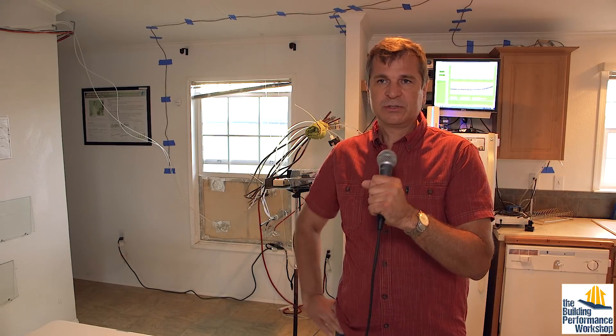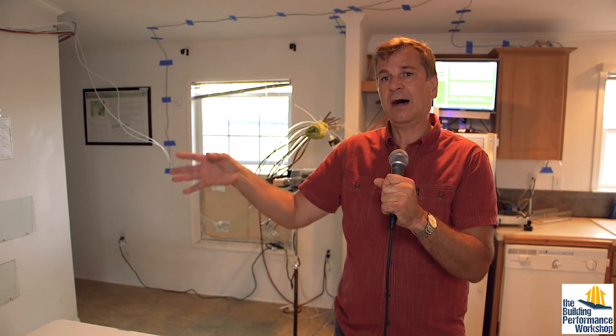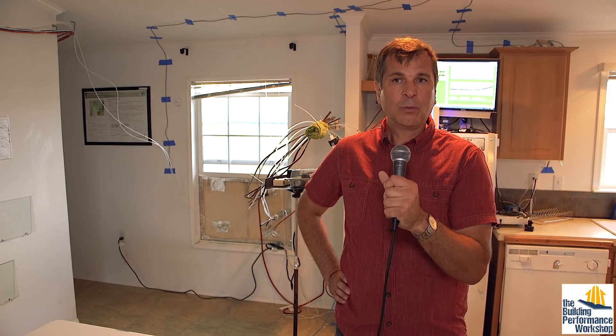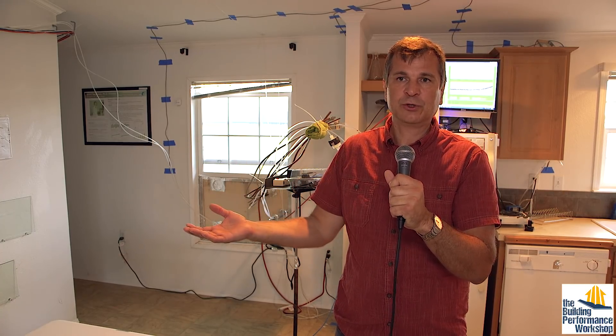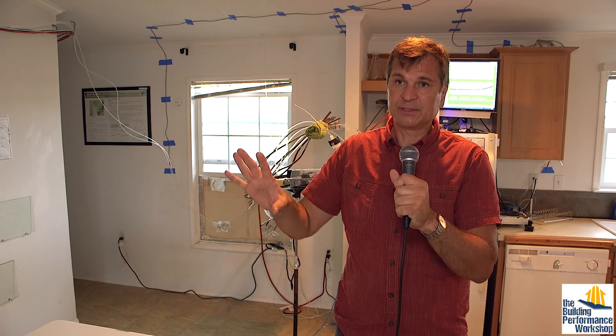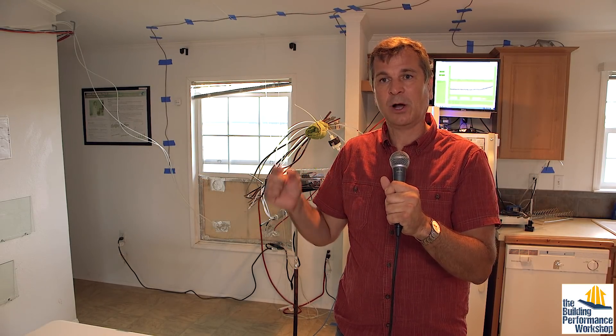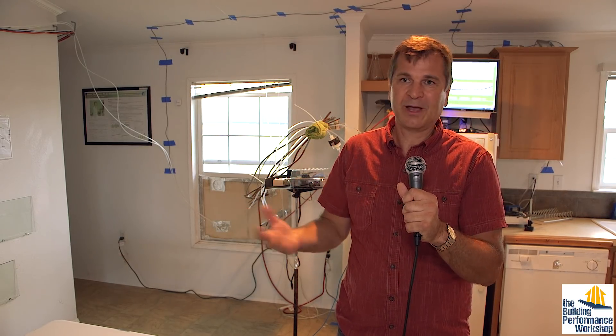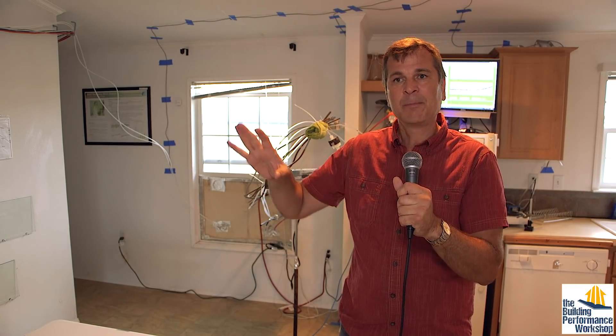In a typical residential home, we have an air system. We use air to distribute energy - cooling or heating - through the house and provide thermal comfort. In a typical home, we have on-off control of the air conditioning system, which means that when we have the right temperature, the system is off. The fan stops moving air through the air handling unit, through ducts, and through diffusers. But that doesn't mean you've stopped air circulation in the home - air circulation is driven by many factors. Pretty much if you move, you're going to drag a little bit of air, but that's not so significant compared to air circulation driven by temperature difference.